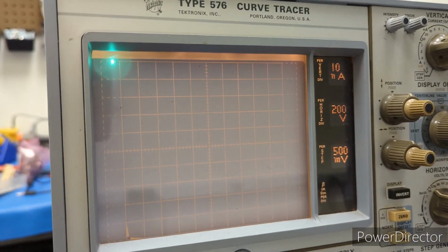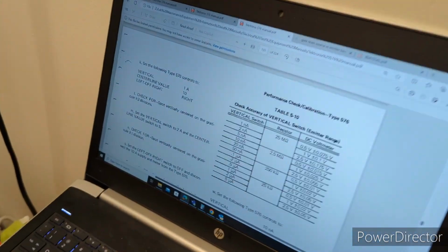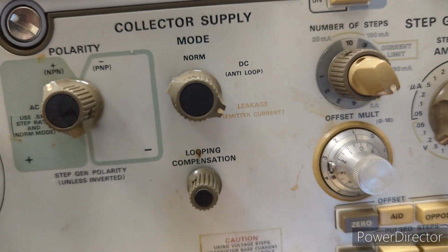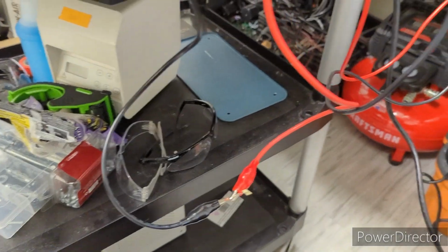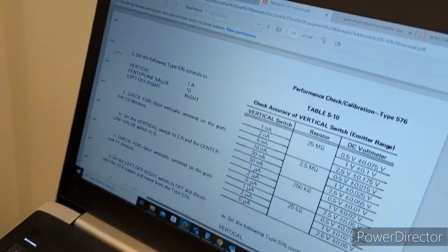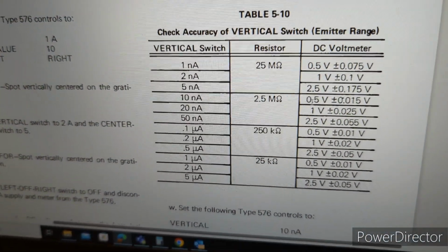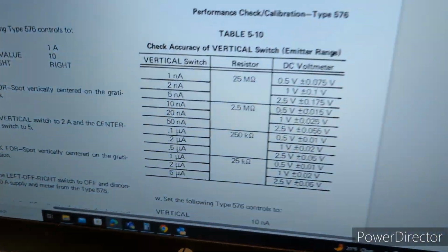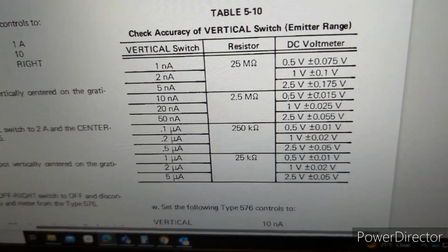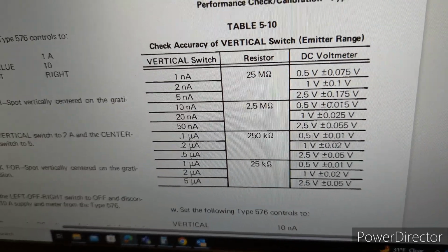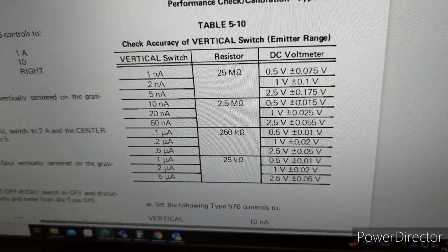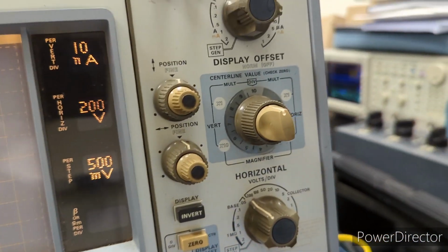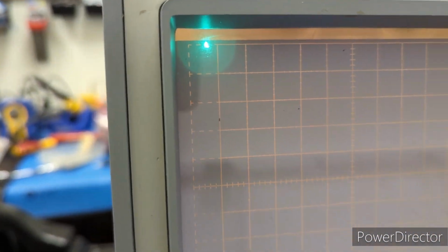Alright, so now it's asking to check the vertical switch for accuracy in the emitter range. So setting that mode to leakage for emitter current. And then I've got a 2.5 mega ohm resistor. This is the only precision resistor that I have that matches the specs that the service manual asks for. So again, it gives you another one of these nice tables. For the vertical switch at 10 nanoamps on the 10th horizontal graticule line, if you move the trace to that line, you should be seeing 0.5 volts on the meter, and we are. So again, the vertical switch is looking accurate, getting the readings that we should.